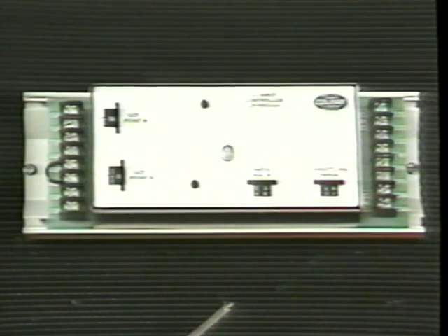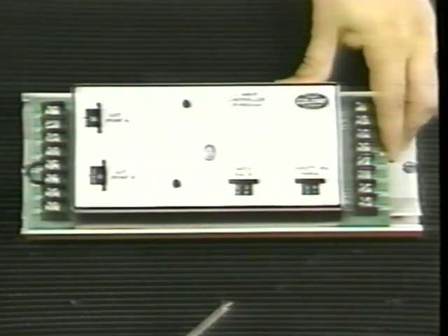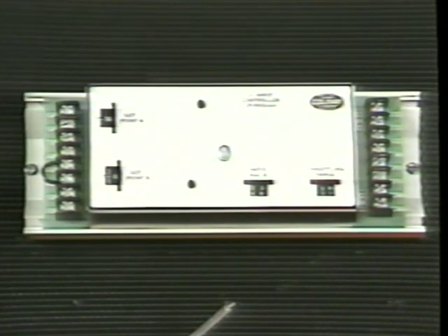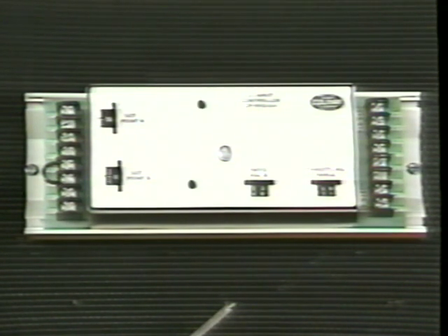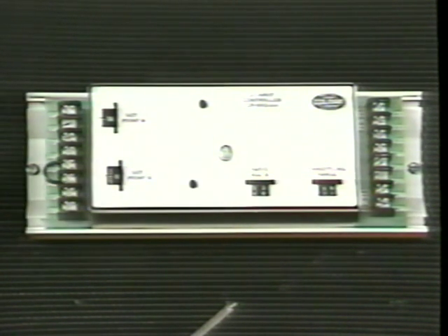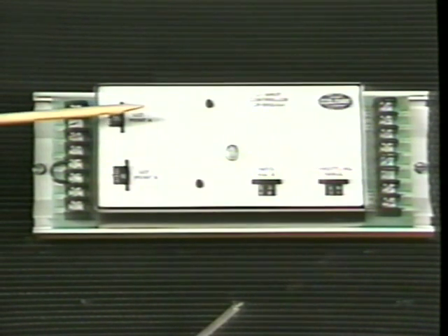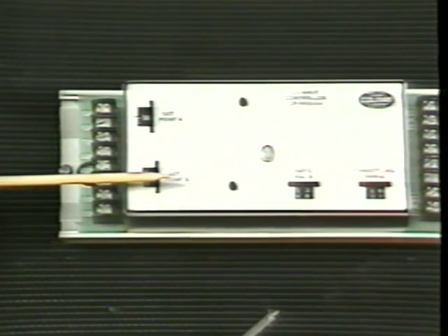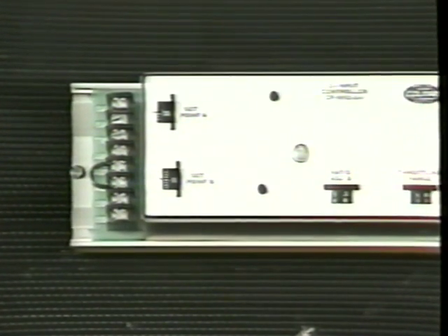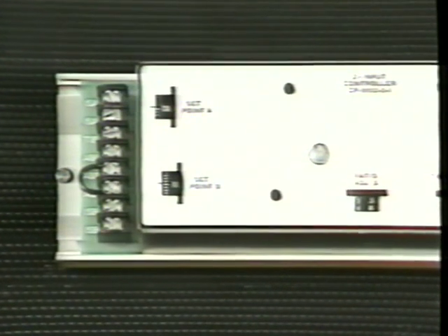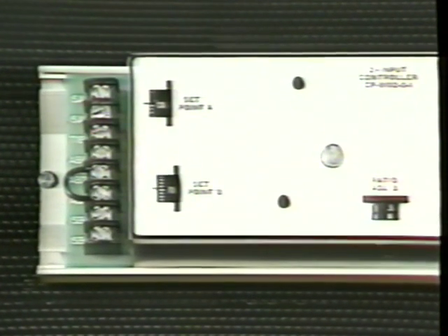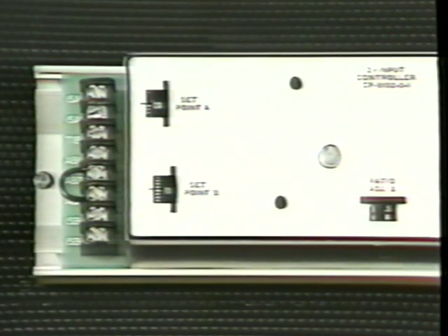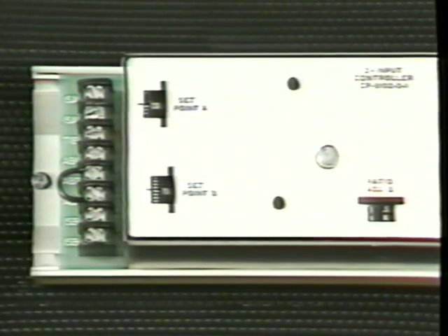The module itself is track-mounted on a provided 3 7/8 by 11-inch plastic track. And it'll operate at ambient temperatures between +40 and +135 degrees Fahrenheit. It consists of 2 sensor input bridges, Bridge A, the control sensor, and Bridge B, the reset sensor, and an operational amplifier which generates a 1 to 15 volt DC control signal. Externally, the following terminals and adjustments are accessible.